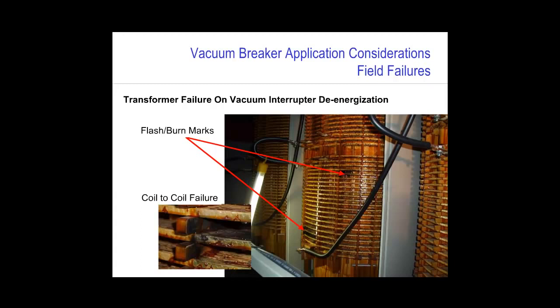Early applications of medium voltage vacuum circuit breakers applied in close proximity to substation transformers have yielded some somewhat disastrous results. I've shown here a photo of a failure on a transformer that was very closely mounted to a vacuum interrupter, and in this case there were flash burn marks on the transformer, and after it was returned to the factory it was determined that there was a coil-to-coil failure.